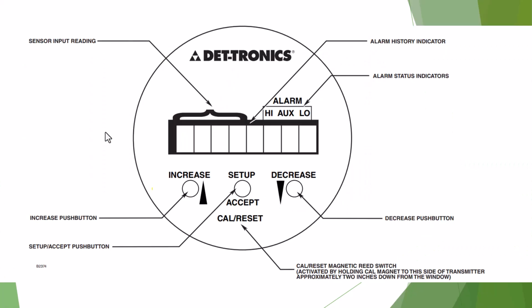Okay, here's the Det-Tronics U9500 interface. Here's the increase push button. The setup push button is for if you have a new Det-Tronics U9500 transmitter. You have to set up the high alarm, low alarm, and the span. You just push this setup push button, and use increase and decrease. You'll find the menu. So here is the cal or reset. This one is the interface, this display. Here is the sensor reading. Here are the high alarm, low alarm, and auxiliary alarm showing here. Okay, this is the alarm indicator.